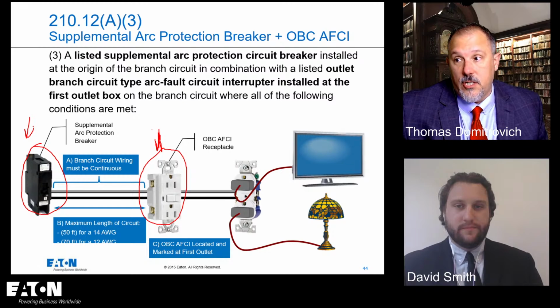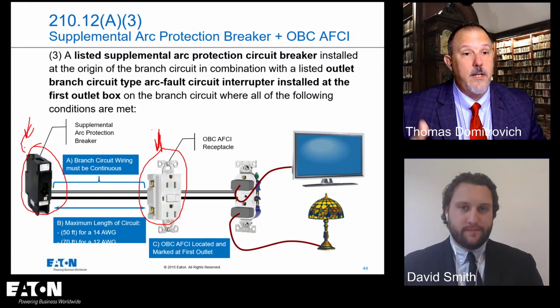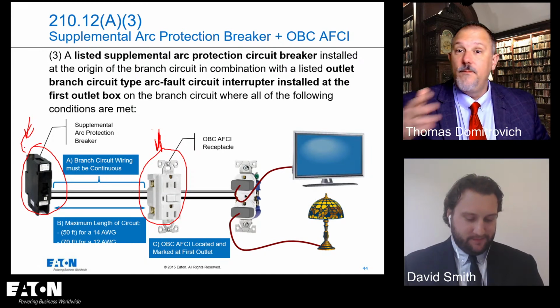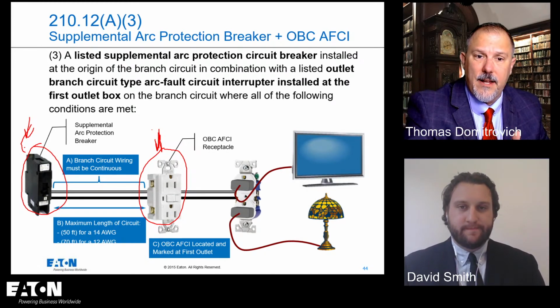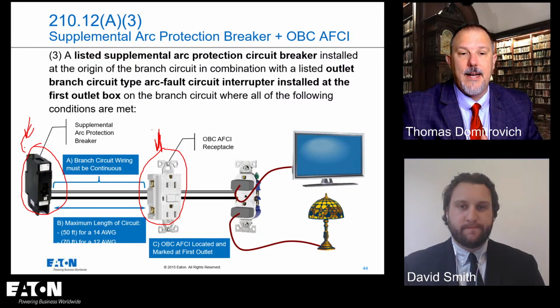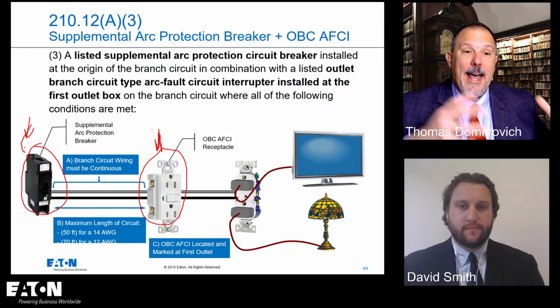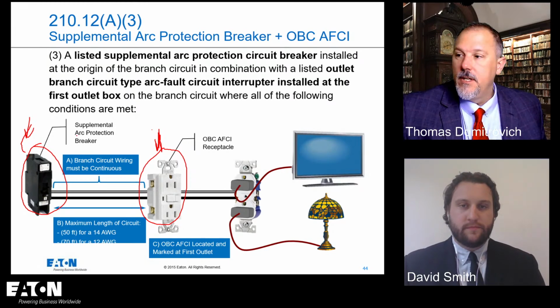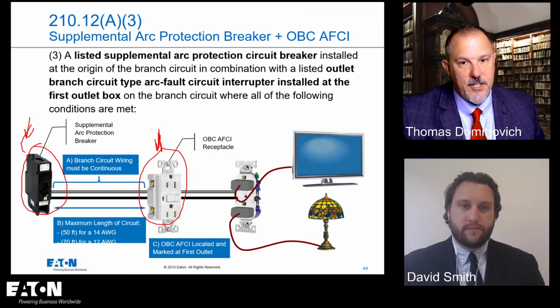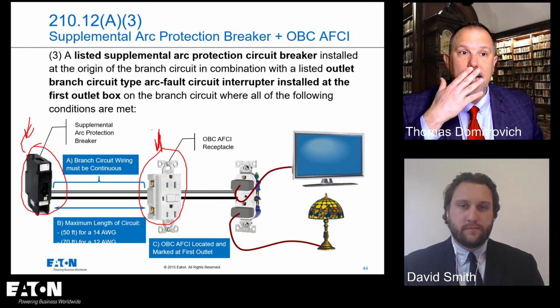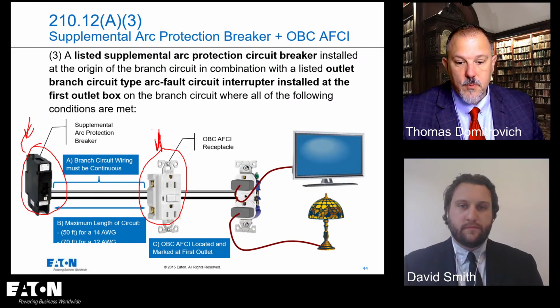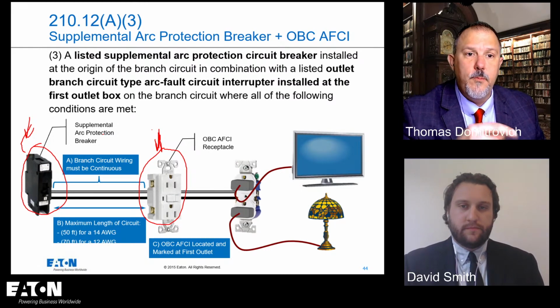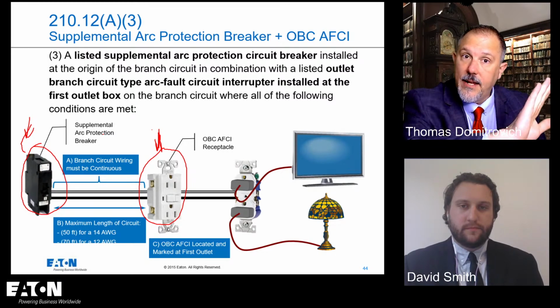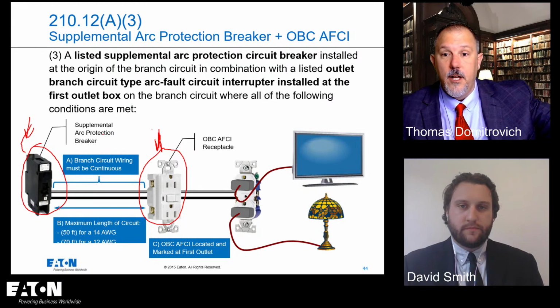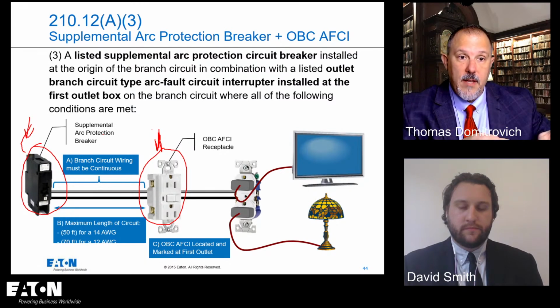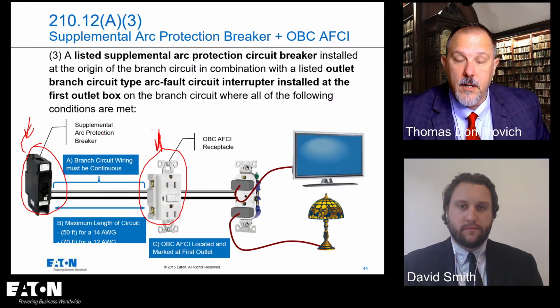And the history behind this has been you protect the entire branch circuit and connected cords. GFCIs are different. GFCIs just look on the tail end, what's plugged in or what's downstream of the GFCI. So at the task group meeting, they were talking about providing a level of protection and permitting the use of an OBC AFCI. And at that time, the receptacle manufacturers were saying, we're not going to bring one to the market unless you put a code requirement in. And they would almost hold hands and stand along the wall and say, we are unified. If you make a change in requiring this, we will bring a product to the market.